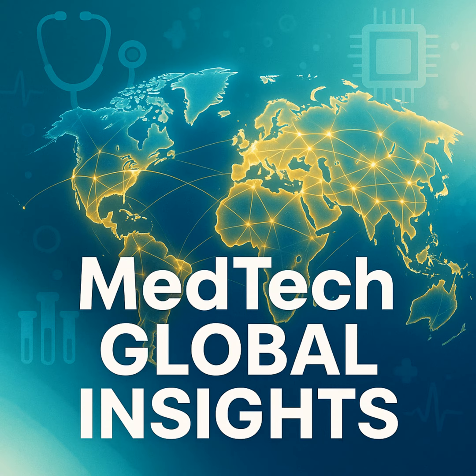It's also crucial to remember that classification is not globally harmonized. A device that is a Class 2 product in the United States might be a higher-risk Class 2B or even Class 3 in Europe under the MDR. This directly impacts the evidence you need, the scrutiny from notified bodies, and your overall global strategy. Understanding these nuances from the very beginning is the key to efficient multi-market access.